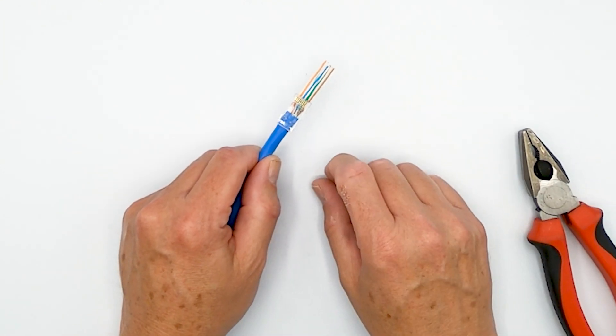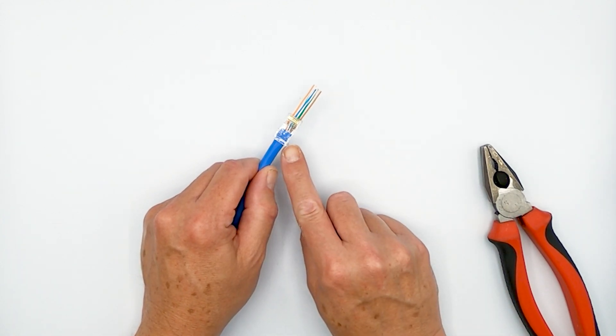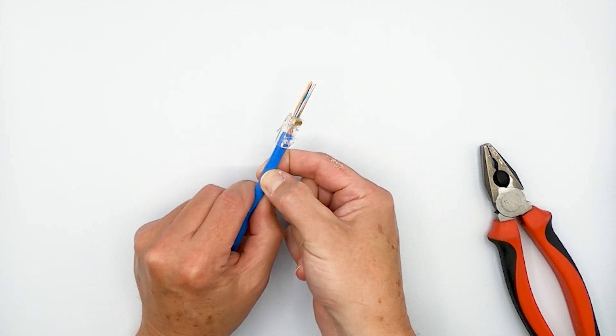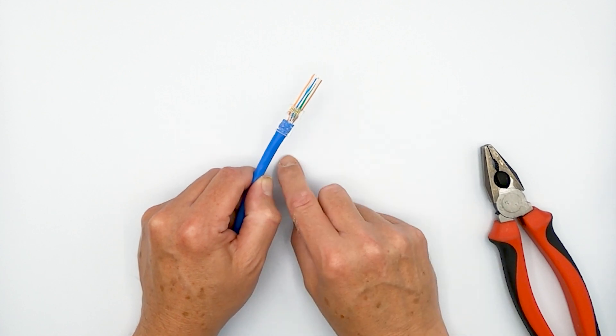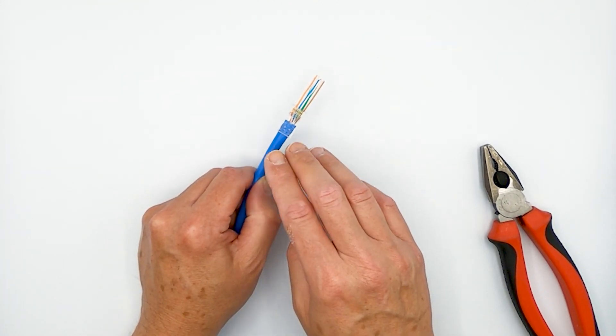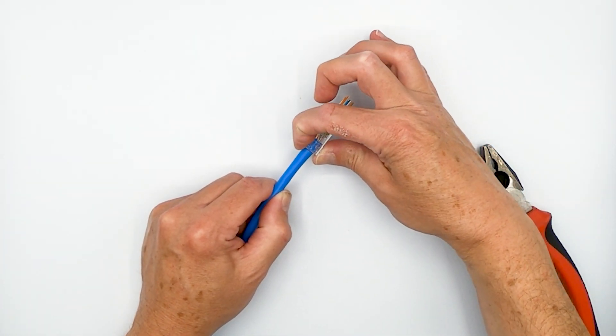And then it simply can't accept cabling at all anymore. I mean, once you get above 6.8 to 6.9 millimeter cable jacket diameter, you know, this happens to be 7.3, you're going to pretty well need to ovalize. It doesn't matter what plug you're using. It doesn't matter what cable you're using. It's just that RJ45s, you've only got so much space to work with on the outside.